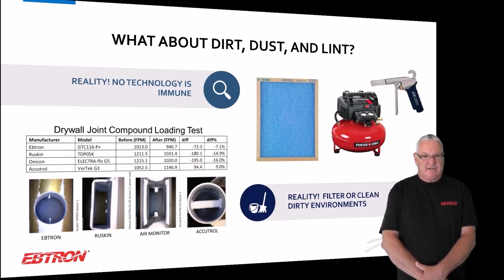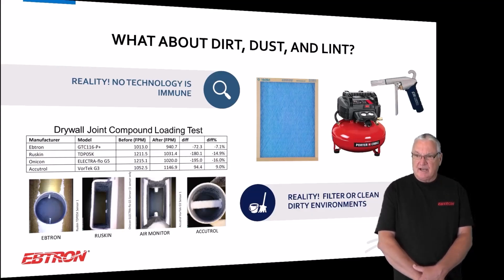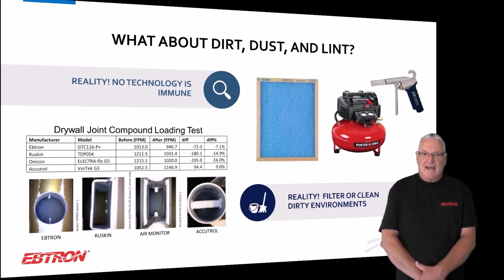We use different materials. We use dry lint. We use wet lint. We use, like in this case, drywall joint compounding. It's about as bad as you're going to get, okay? We do different things to see what we can do to overcome some of the problems of dirt, dust, and lint. And the bottom line is when you start talking about needing measurements that are better than 2% of reading, and needing measurements that are better than 2% of reading for 10 or 15 years, you really need to start to understand that you need to provide a really good environment.